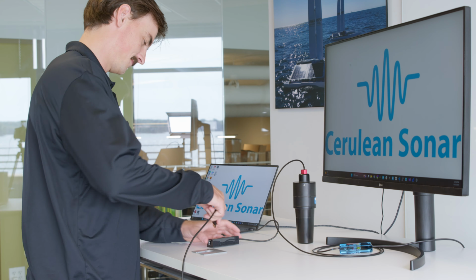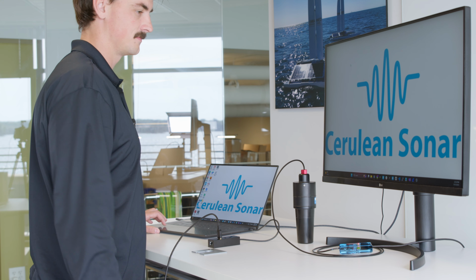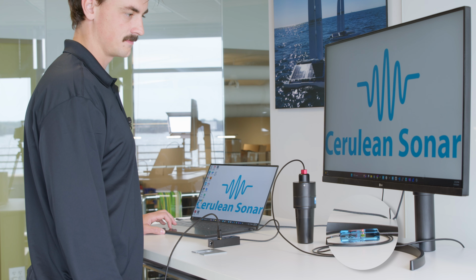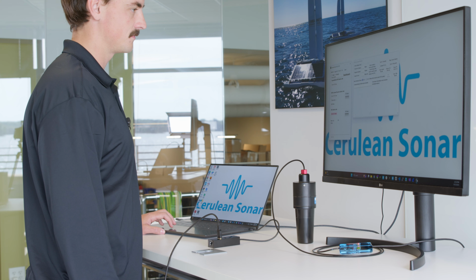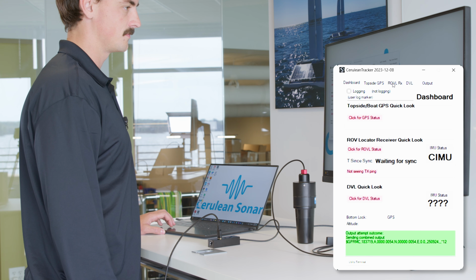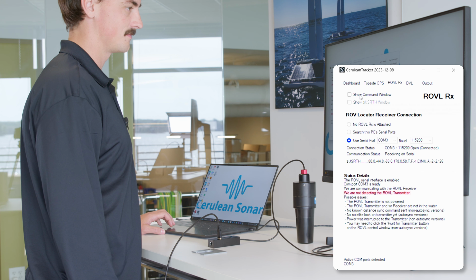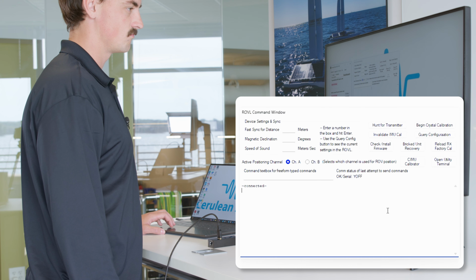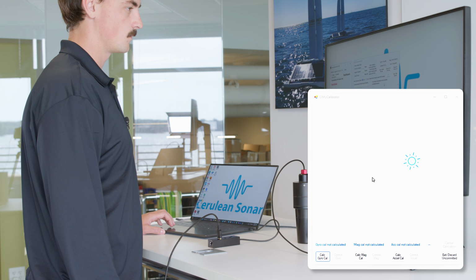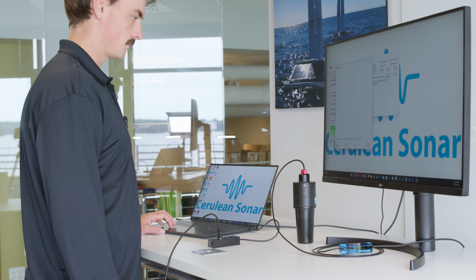First, connect the unit to one of the available USB ports. You can confirm that the unit is on by the LED on the serial to USB cable. Launch the Cerulean Tracker app and select the ROVL RX tab. On this panel, make sure the Show Command Window checkbox is checked. In the ROVL command window, press the CIMU Calibrator button. This will open the CIMU Calibrator window.